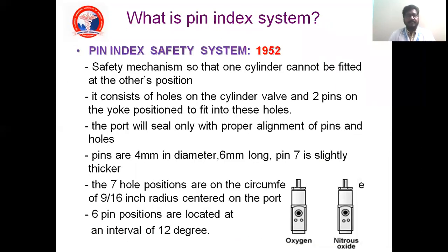What is the pin index system? It is a very important aspect in cylinders. It is one of the safety systems in cylinders in the high pressure system. The pin index safety system was invented in the year 1952, and it is one of the safety systems of the high pressure system, so that one cylinder cannot be fitted at another position. It consists of holes on the cylinder valve and two pins on the yoke position to fit into the holes. The port will seal only with proper alignment of the pins and holes.